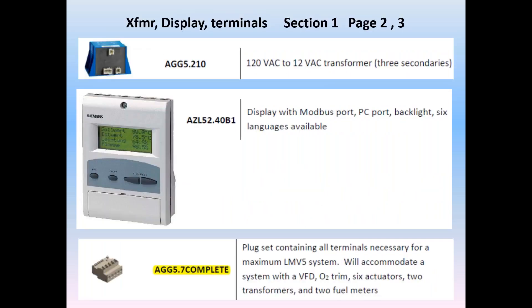Each LMV5 installation will require a transformer that has three secondaries. This provides power for the LMV5's dual processors, the CAN bus network, which includes the LMV5, the AZL display, all of the actuators, sometimes referred to as servos, and finally the PLL module if used for oxygen trim. This AZL is also called an HMI. It is the keyboard display unit that can be used with any of the LMV5 versions, past or present.